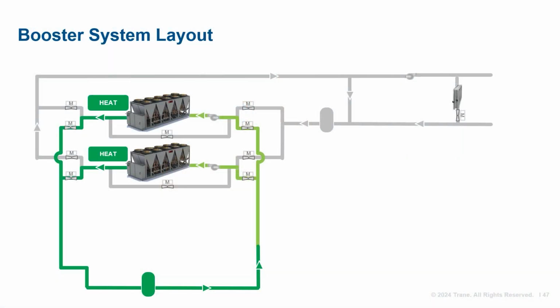The downside to these systems is that adding another unit will increase system cost and may decrease efficiency. This is not a replacement for designing systems to lower hot water supply temperatures, but may be useful in certain retrofit situations. This concept may be used to boost temperatures in various plant layouts and situations. Let's look at how this might be piped in an air-to-water heat pump system. Here we have a traditional air-to-water heat pump system piped in a dual decoupled arrangement. As mentioned earlier, the limitation is that hot water supply temperatures are dependent on ambient conditions and may not be suitable for some retrofit situations.